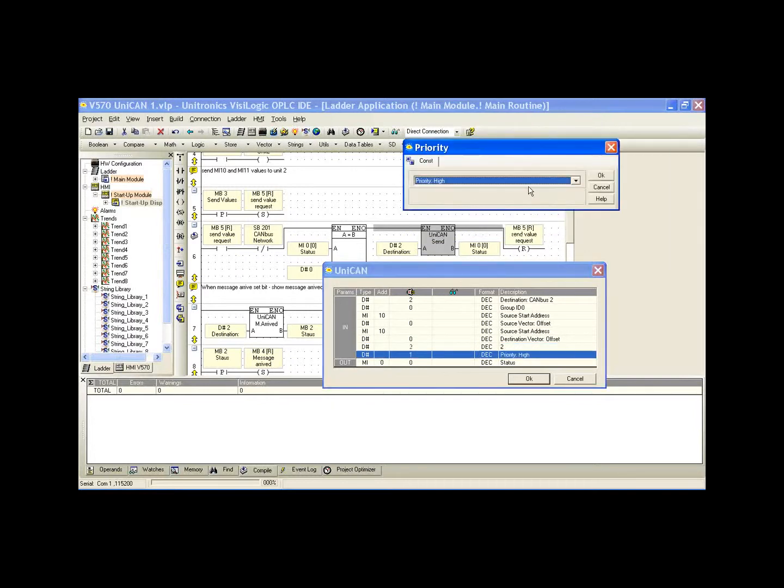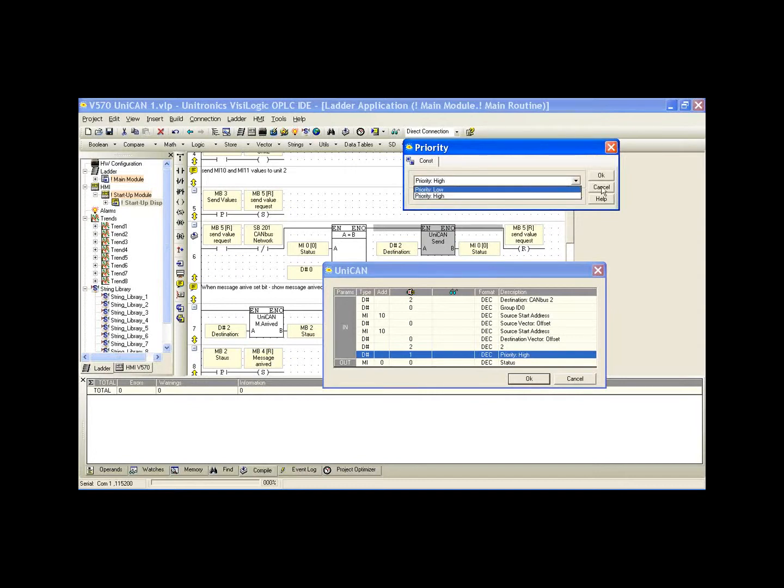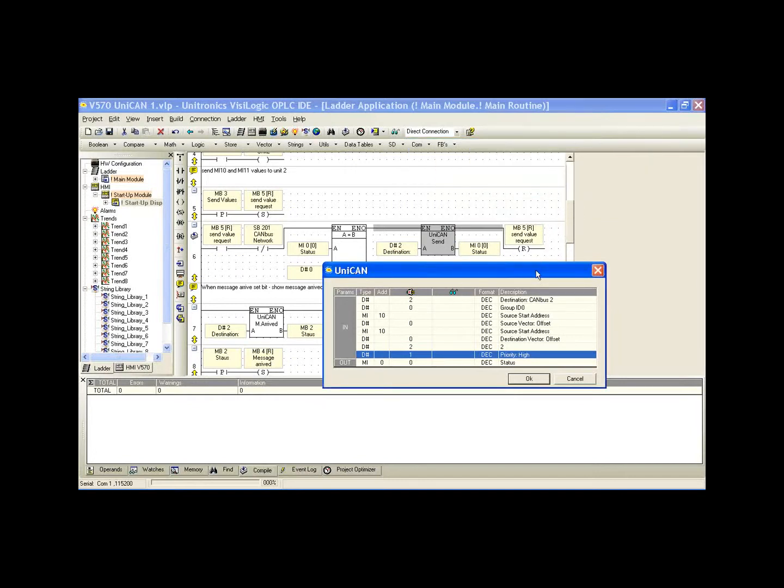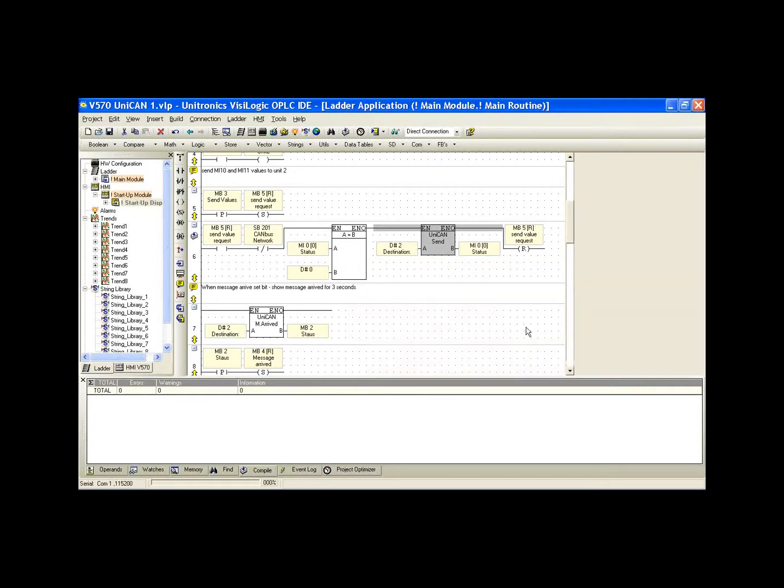In the priority, we can select either high or low. In this case, we've selected high. What the priority does is send the message to either the high or low priority buffer. Each buffer can contain 16 messages. So we can have 16 messages in the high and 16 in the low. All of the high priority messages are sent before the low priority messages. This is our send command.